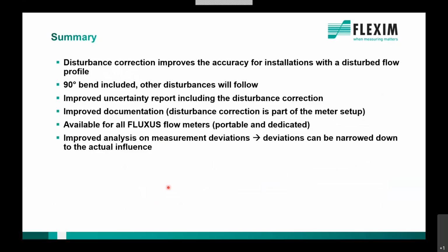Good. As a summary, what did we learn today? The disturbance correction improves the accuracy for installations with a disturbed flow profile. That means almost every application in the field profits from that, because you nearly have disturbed flow profiles in every application you find, unless you have many Ds of straight lengths. The 90-degree bend in the Fluxus meter is now included. Other disturbances will follow. If you have other disturbances, use that correction anyway, because it makes the correction in the same direction.